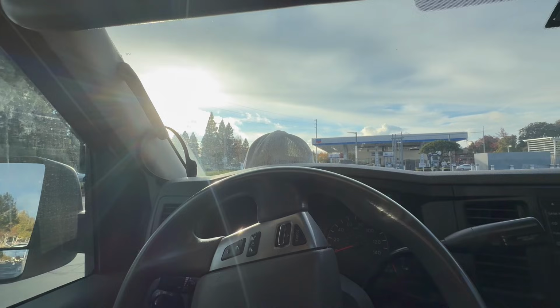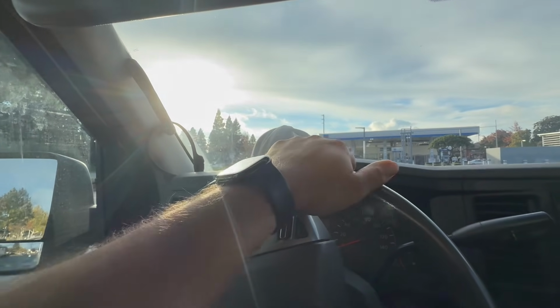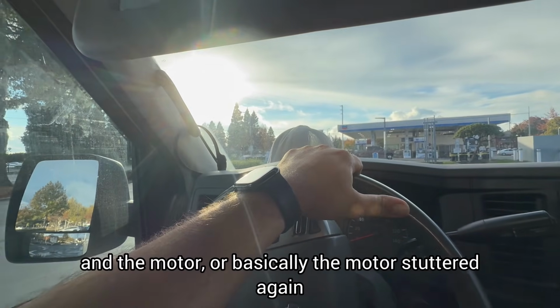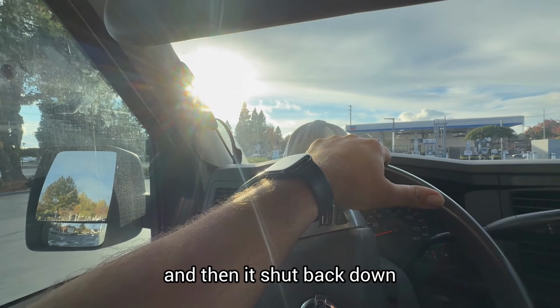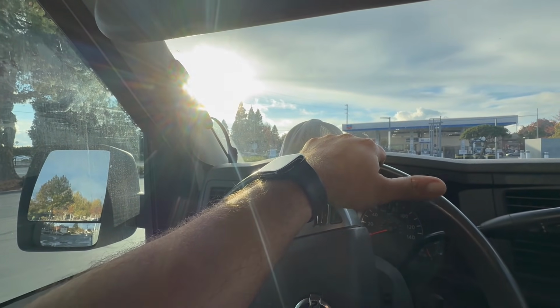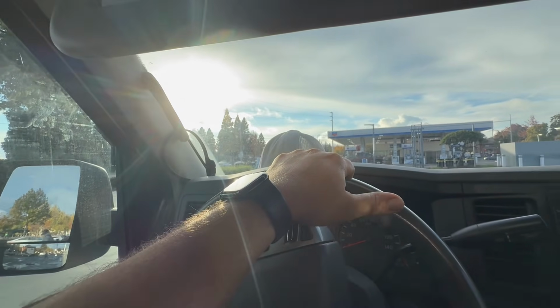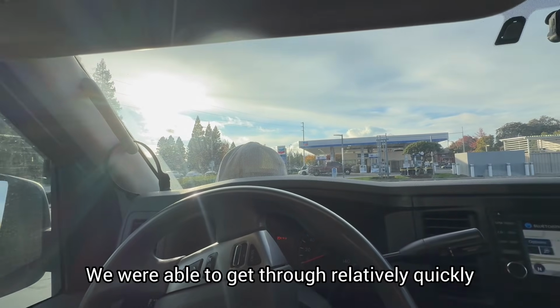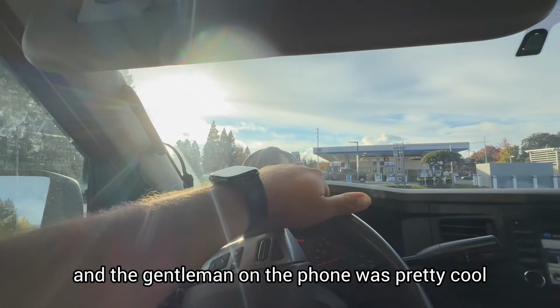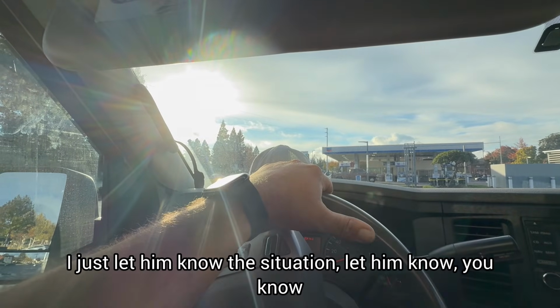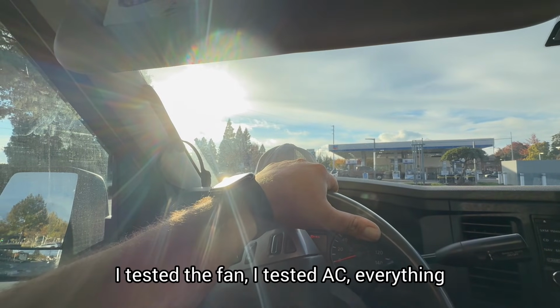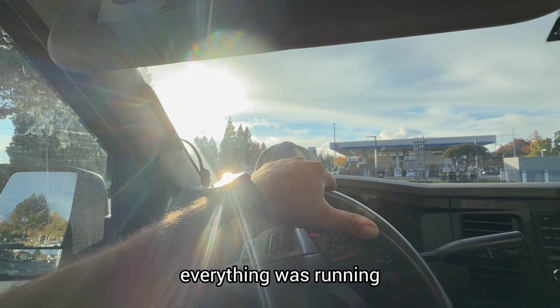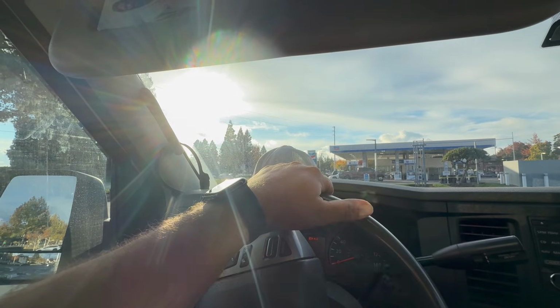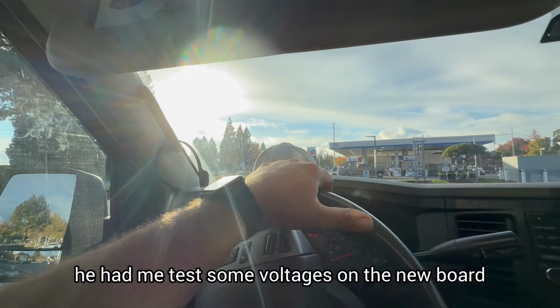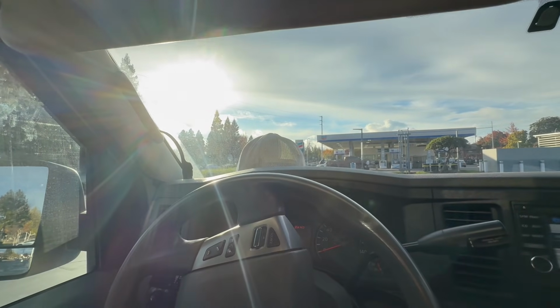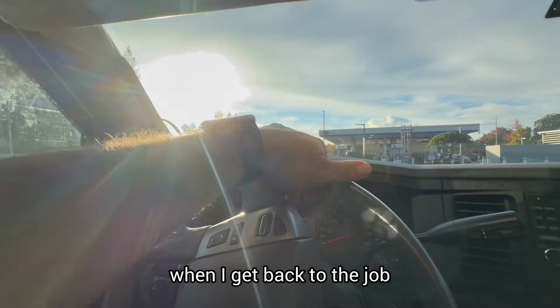So I put in that board and the motor, but the motor stuttered again. It came on briefly and then shut back down and went off on high limit, so I was a little frustrated. I called tech support, thankfully we got through relatively quickly, and the gentleman on the phone was pretty cool. I let him know the situation, that I tested the fan, tested AC, everything on the old board was running, but just the heat, the blower wasn't kicking on. So he had me test some voltages on the new board, and I'll show you guys those when I get back to the job.